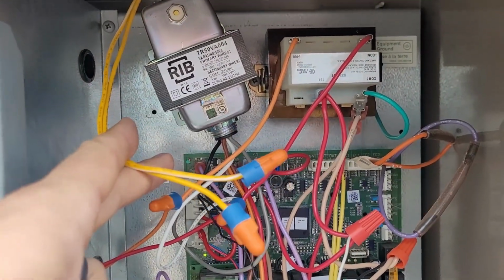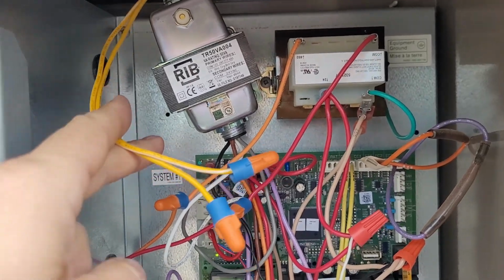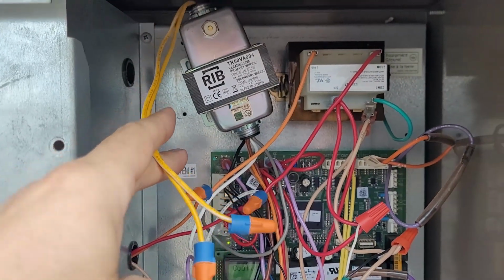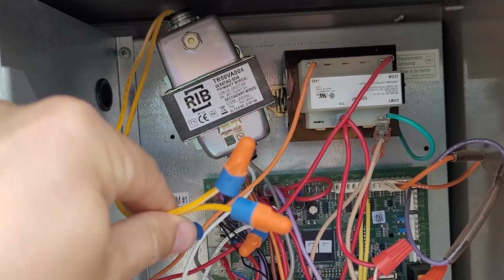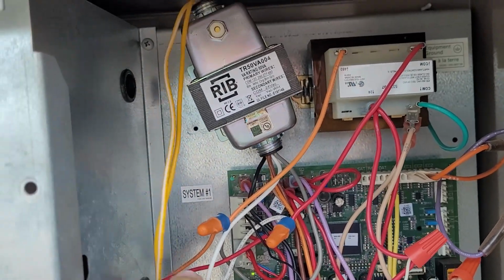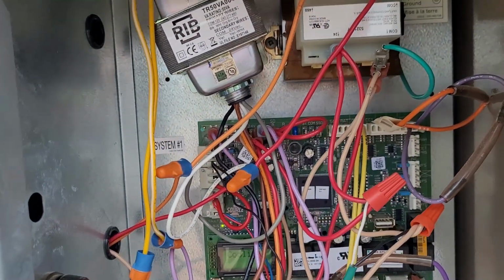So here I have a 24 volt transformer that's outputting 36 volts. And so we know that something is wrong on the high side. The low side's putting out 36 instead of 24. Got to be something wrong on the high side. So let's see what happened.